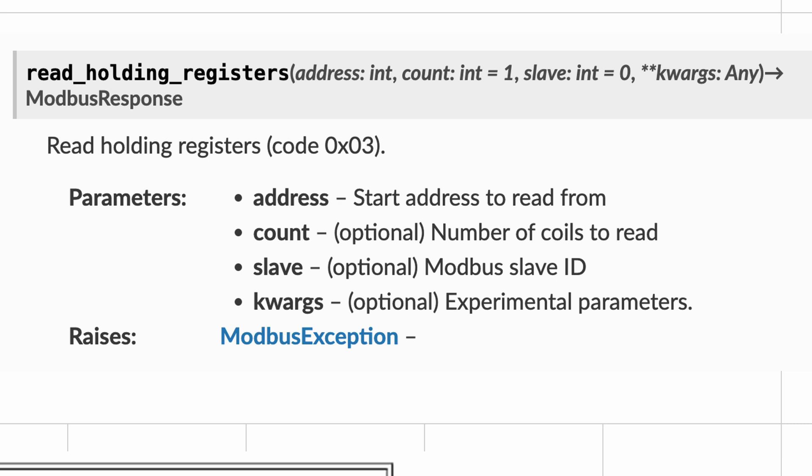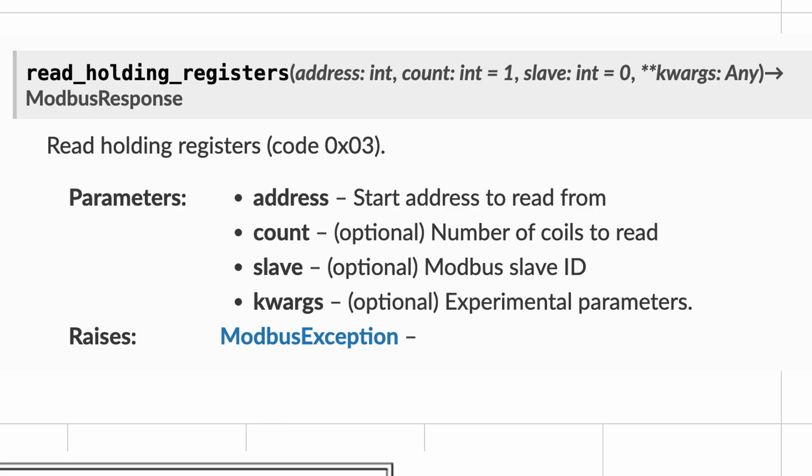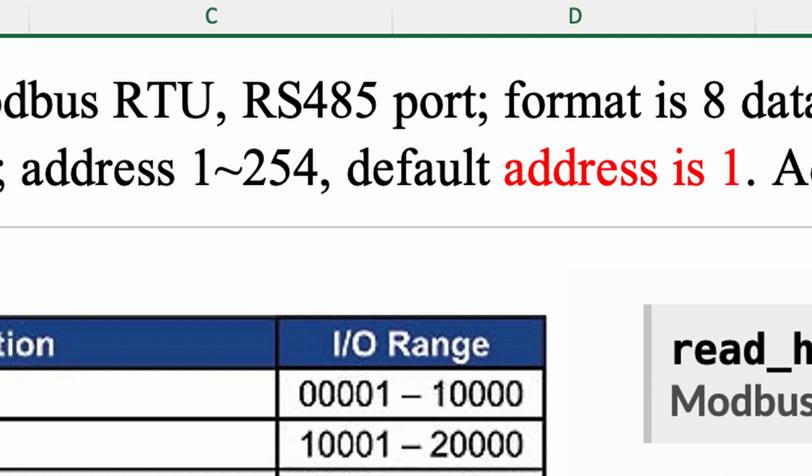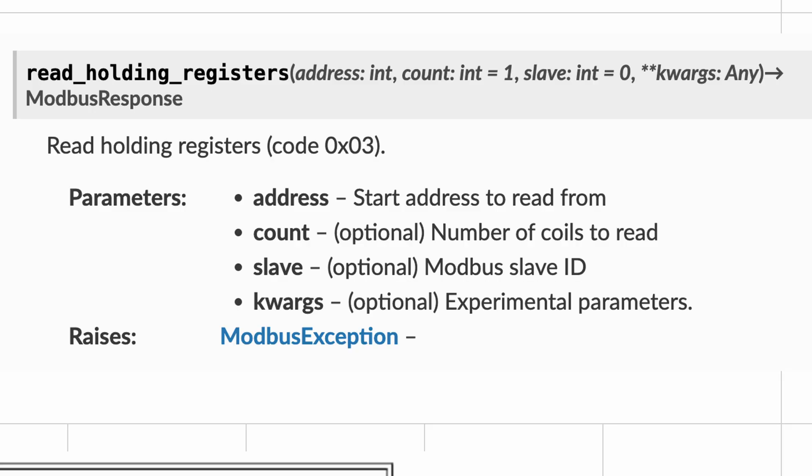PyModbus has a function called read_holding_registers. It takes three arguments: address, count, and slave (an integer). The doc also confirms its code is 0x03, which is hexadecimal 3. Now we need to fill the three parameters. The slave is the Modbus slave ID — back in the sensor datasheet, it says the address range is 1 to 254 with a default of 1, so that's likely the slave ID and we fill slave=1.